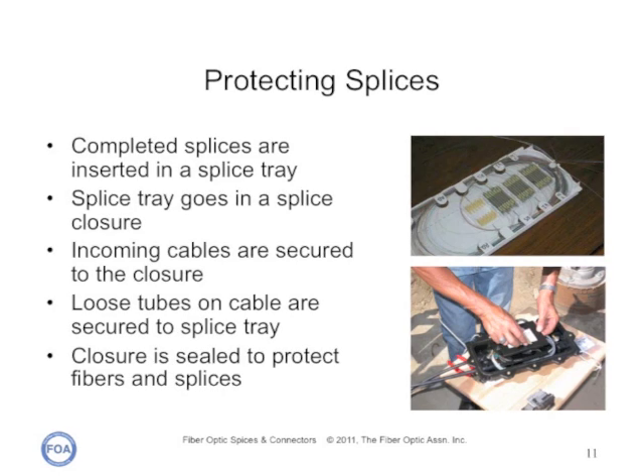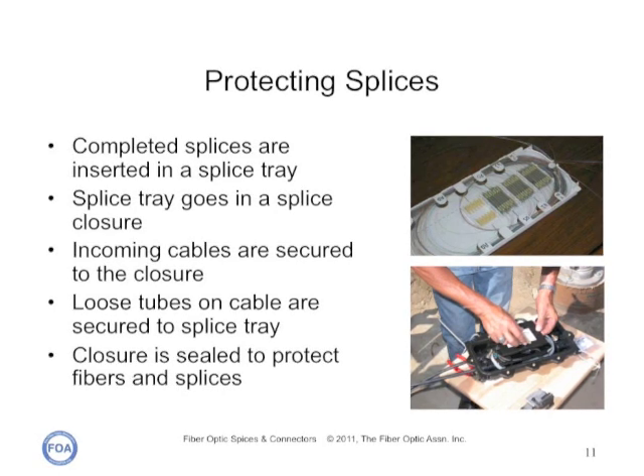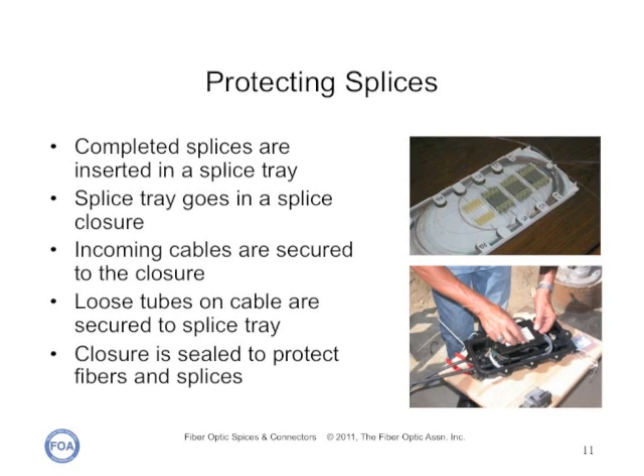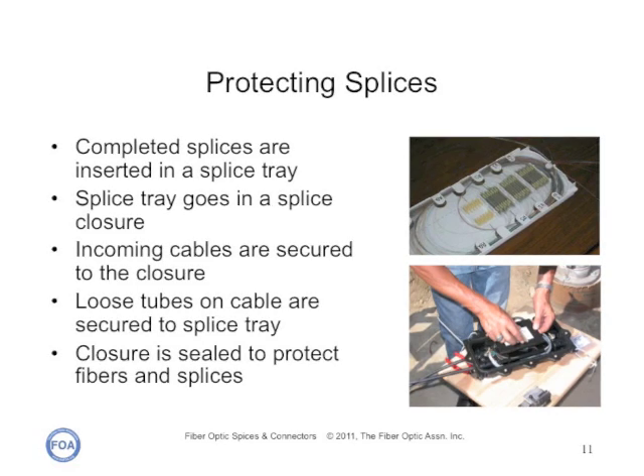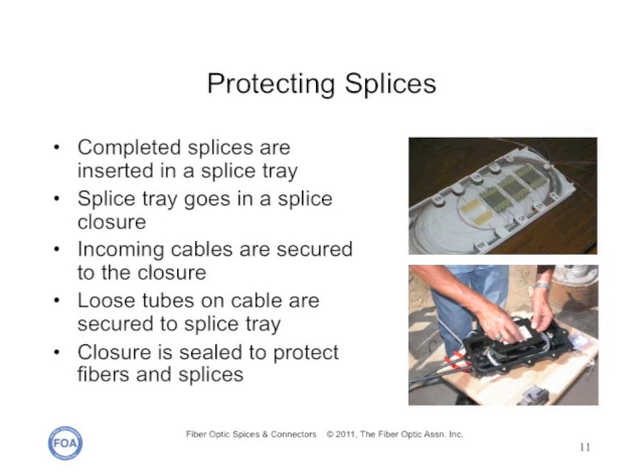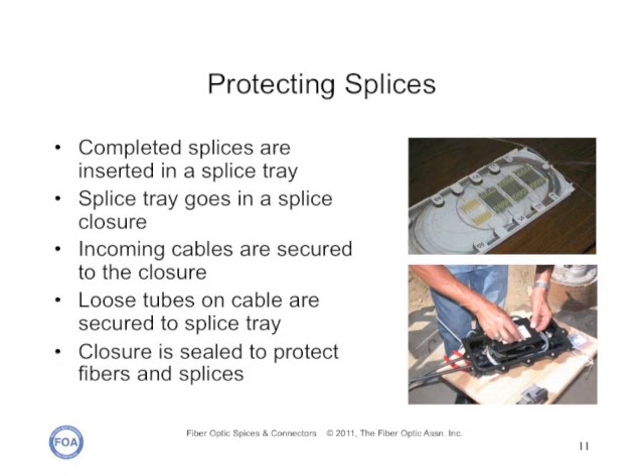After the splices are made, they need protection from the environment — they don't have all the mechanical hardware of a connector. Completed splices are inserted in a splice tray, and the splice tray goes in a splice closure. The incoming cables are secured to the closure, and on loose tube cables, the tubes of the cable are secured to the splice tray. After all the splices are completed and the trays are placed in the closure, the closure is sealed to protect the fibers and splices from the environment.